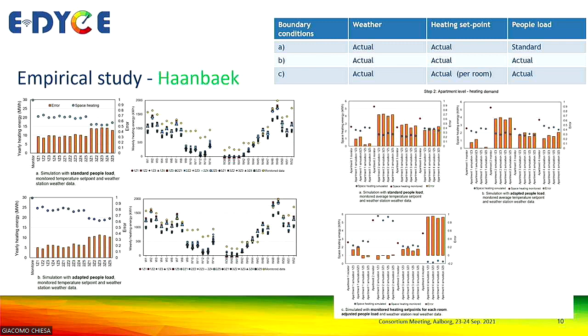You can see on the x-axis the models named, and on the y-axis we see the yearly heating energy demand. And the orange bars are the errors produced for every model when we compare the operational monitoring data with the model simulations. What we get here is that many models perform in a more or less similar way. The model that has the highest results is the one that uses the space heating as a water-based radiator, designed as a whole heating system in the model.